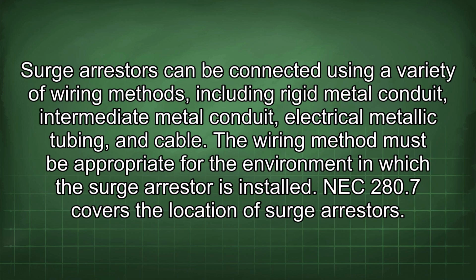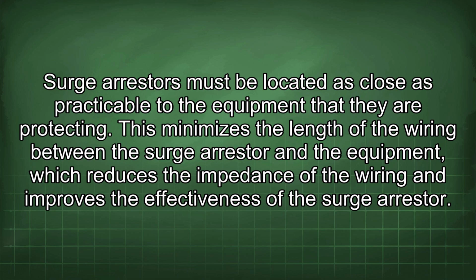NEC 280.6 specifies the wiring methods that are permitted for connecting surge arrestors. Surge arrestors can be connected using a variety of wiring methods, including rigid metal conduit, intermediate metal conduit, electrical metallic tubing, and cable. The wiring method must be appropriate for the environment in which the surge arrestor is installed. NEC 280.7 covers the location of surge arrestors. Surge arrestors must be located as close as practicable to the equipment that they are protecting. This minimizes the length of the wiring between the surge arrestor and the equipment, which reduces the impedance of the wiring and improves the effectiveness of the surge arrestor.